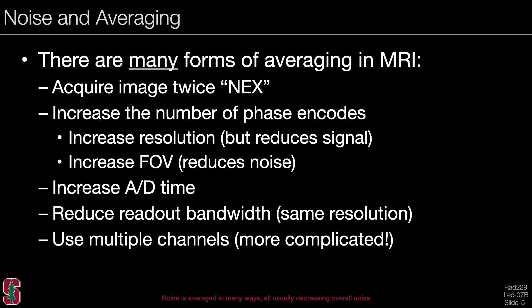There are many forms of averaging in MRI. We can acquire an image twice, often referred to as two averages or two NEX. We can increase the number of phase encoding lines — by increasing resolution, though this will reduce signal as we'll discuss later, or by increasing the field of view, which will reduce the noise. You can increase the acquisition time or A-to-D time, reduce the readout bandwidth and keep the resolution the same, or use multiple channels, which is another form of averaging that will be dealt with in the next lecture.